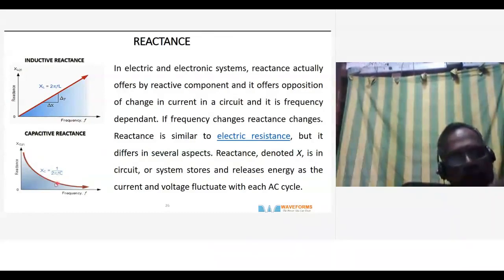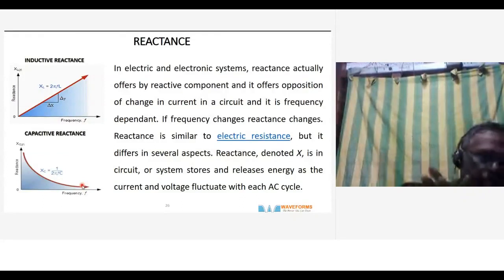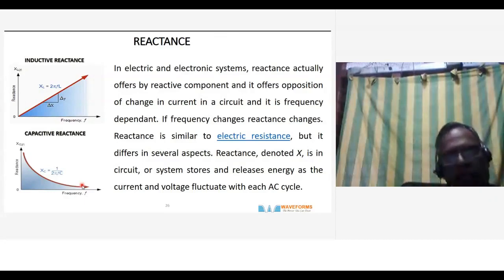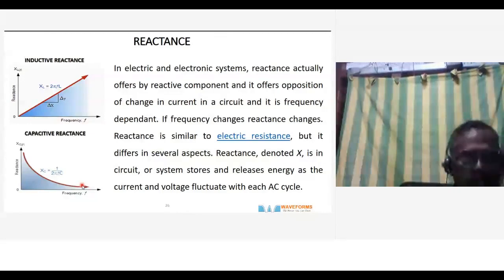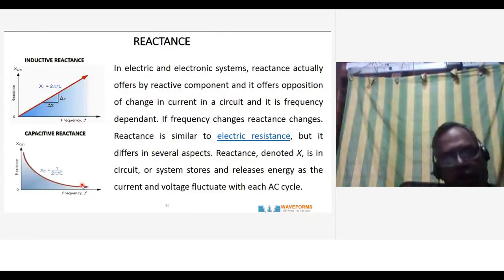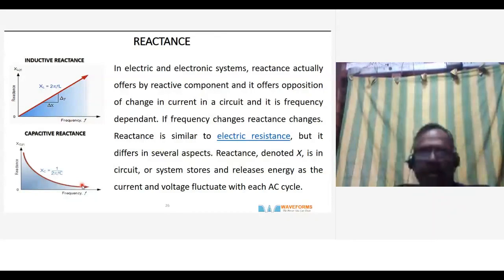So you will see this graph. As the frequency increases, the reactance of the capacitor at a higher frequency becomes very low, and it becomes open when the frequency is low. So this principle is used basically for tuning or mitigating harmonics. By manipulating inductance and capacitance, or intelligently using a mix of inductance and capacitance, we try to mitigate harmonics using a broadband filter or tuned filter.